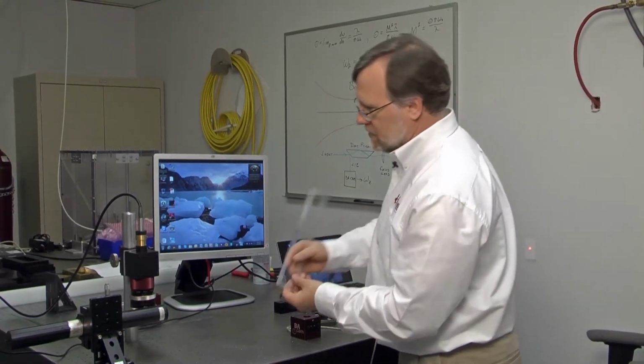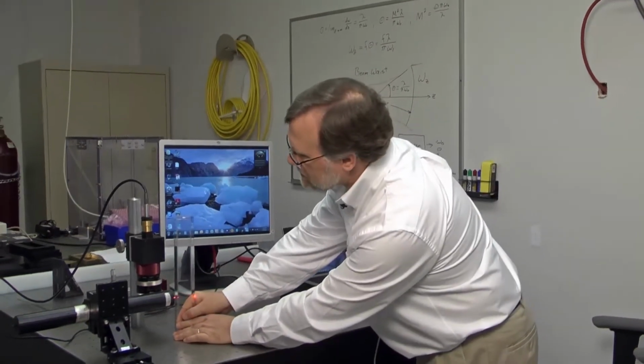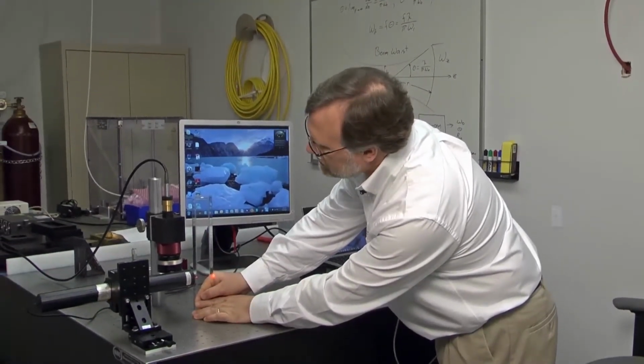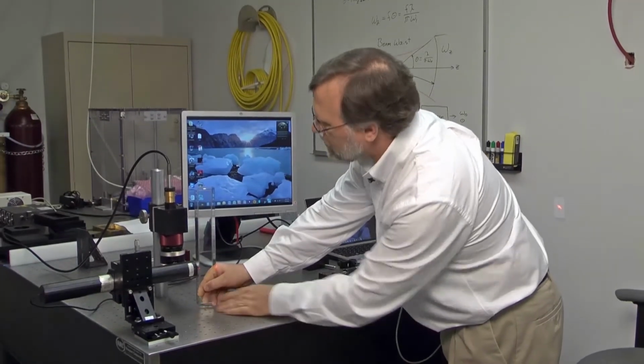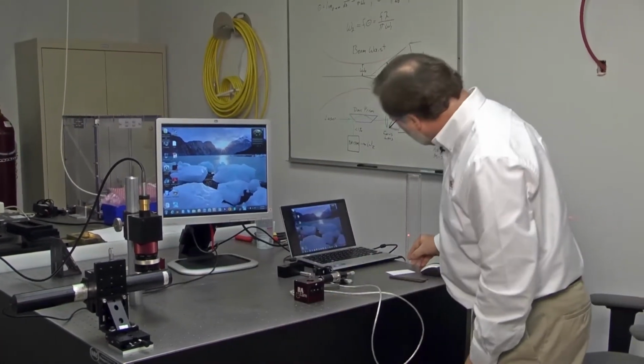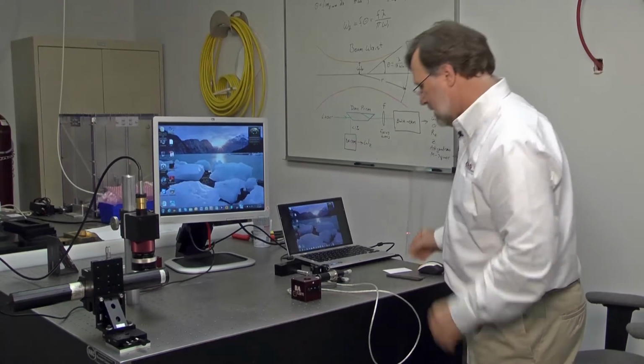Basically, we just make sure that the height of the laser is matched at a distance. So here we go, about 9.7 millimeters. And over here, we're at the right level.